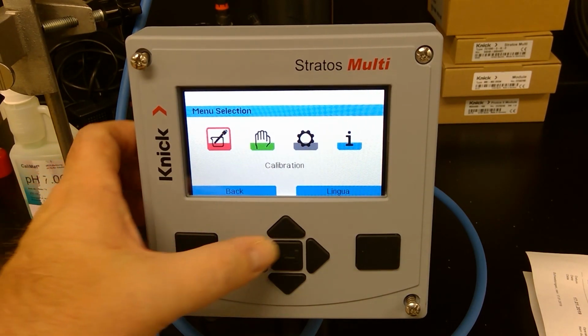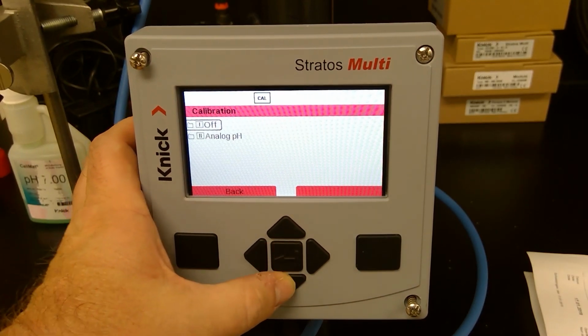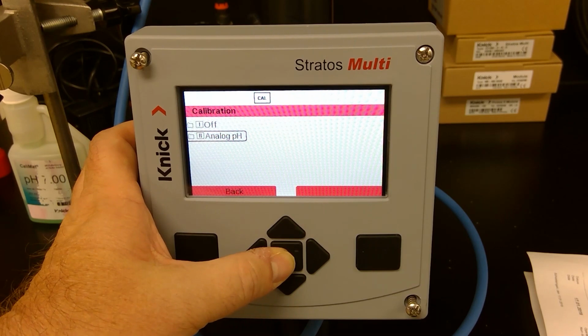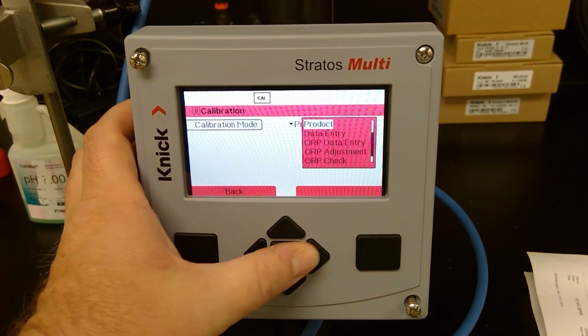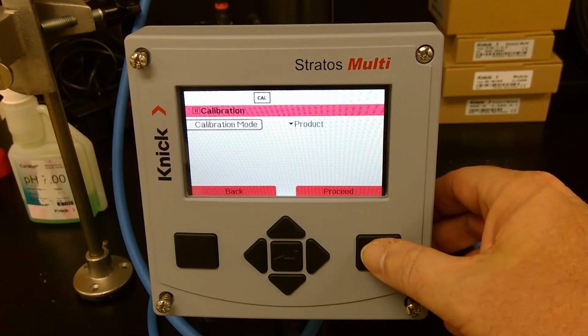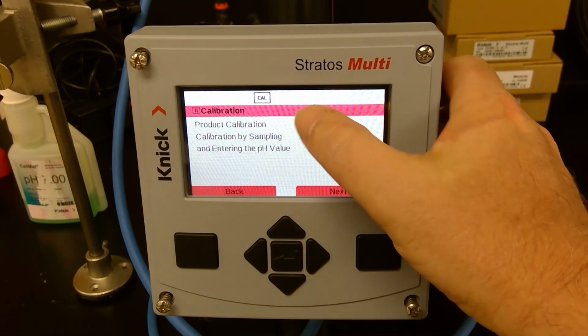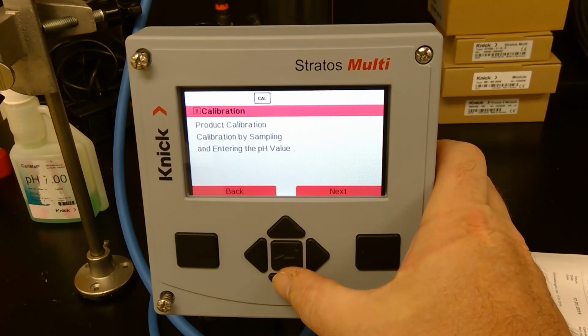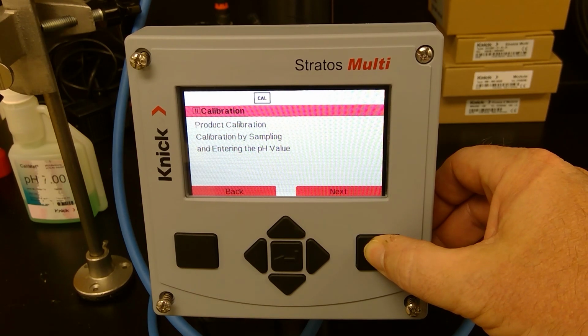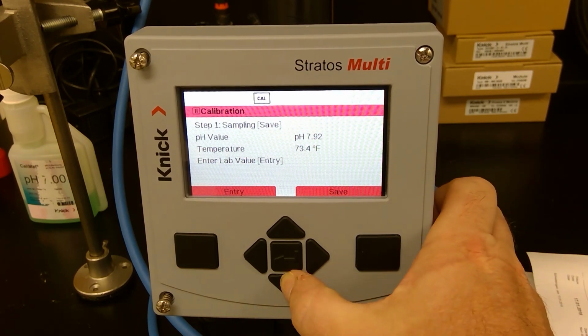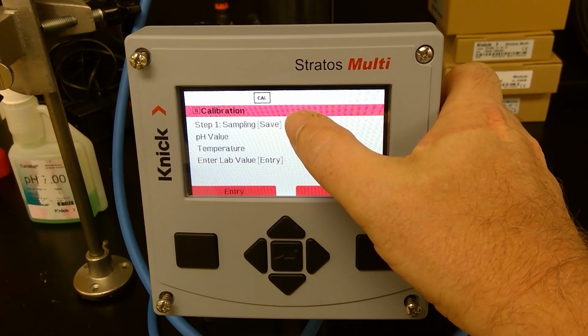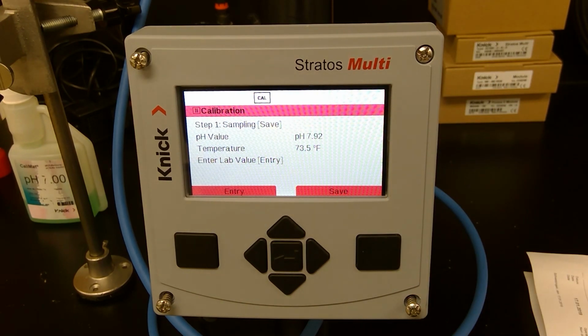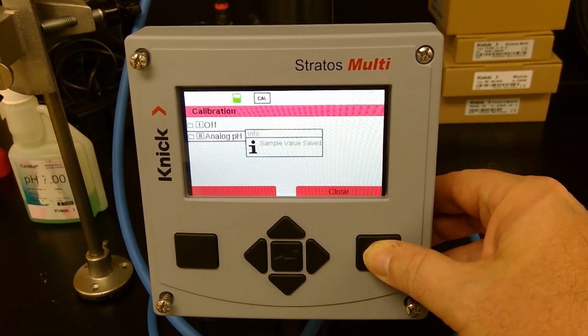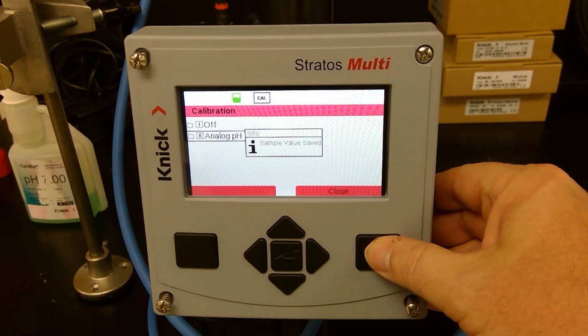So to do that, I hit menu, I hit enter for calibration, and then of course I'm going into channel 2 analog pH, and it's already set for product cal. So I hit proceed. Product calibration, calibration by sampling and entering pH value. So what you do is you hit next at this screen. So you see that it says it's sampling, and we're going to save the current pH value that it's reading. Okay, so we don't have the lab sample value yet. So I hit save. Then I hit close.